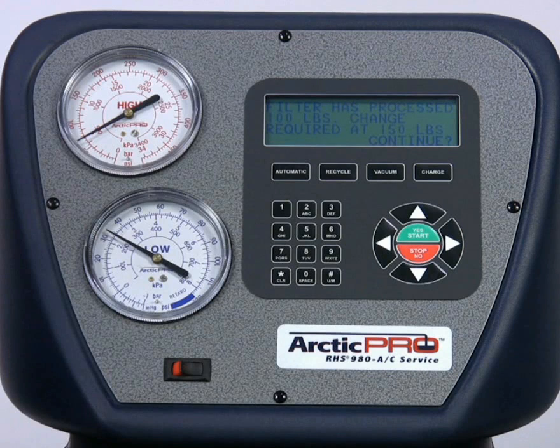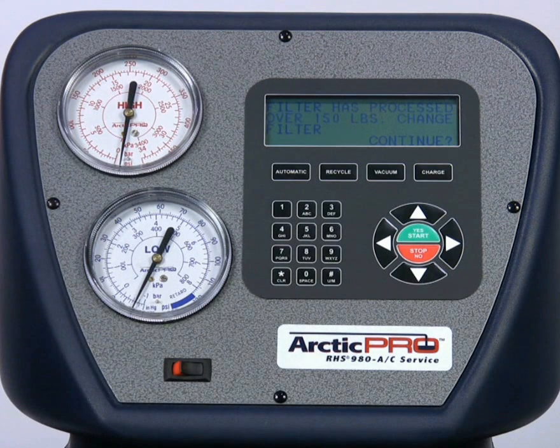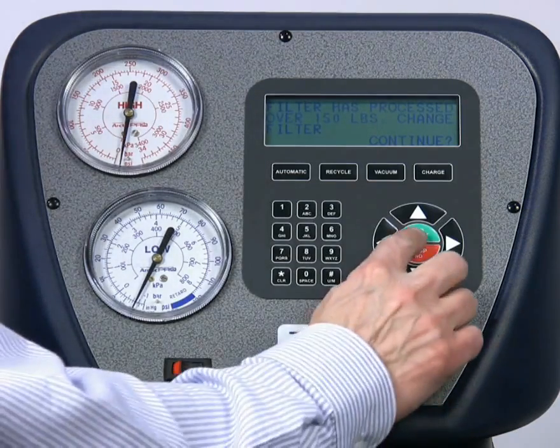An alert will display when filter life reaches 100 pounds. The RHS980 will automatically shut down when the filter has processed 150 pounds of refrigerant. At this time, a new filter must be installed and its corresponding serial number entered to restart the RHS980. To begin the combo filter replacement procedure, press the green Yes button. Now let's replace the combo filter.